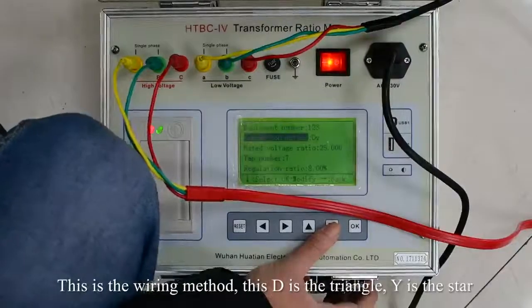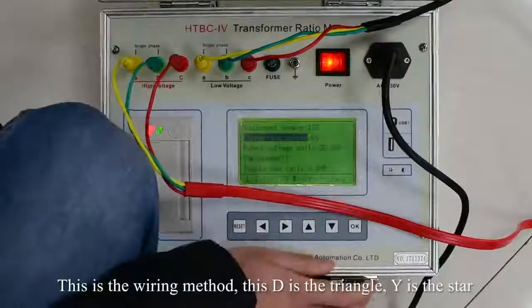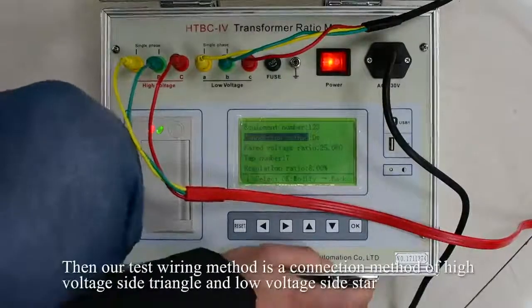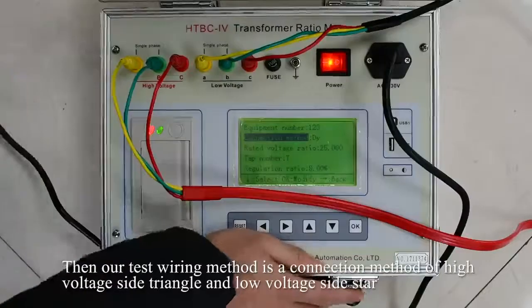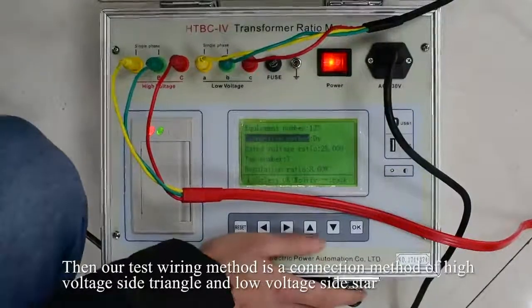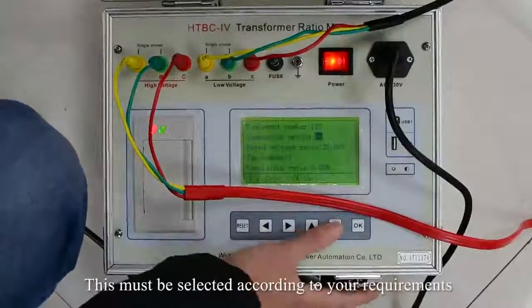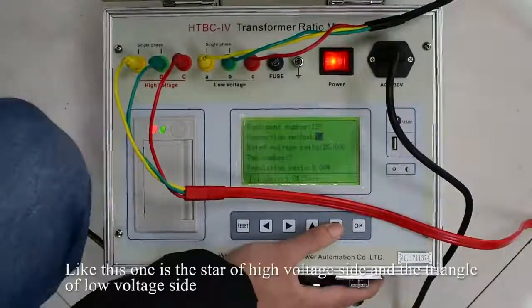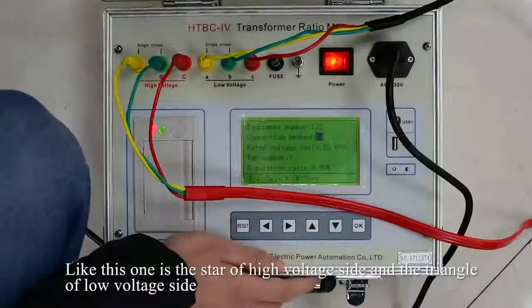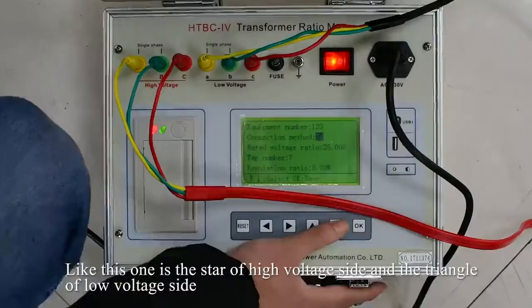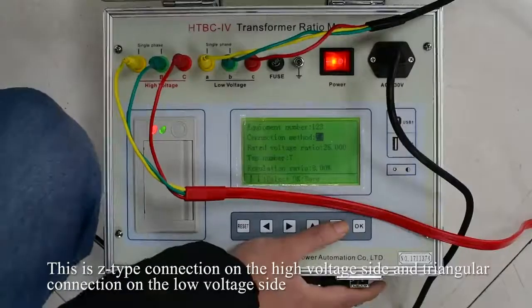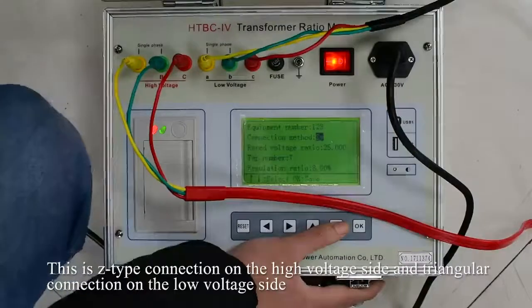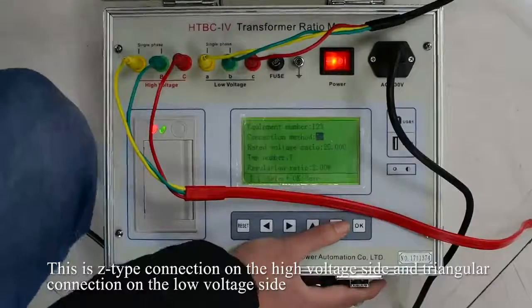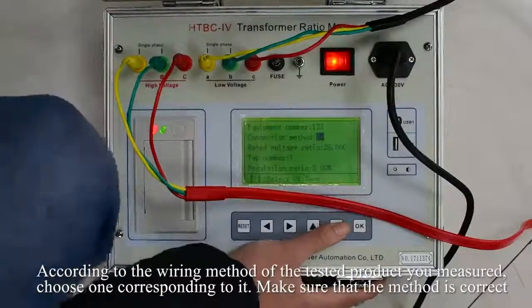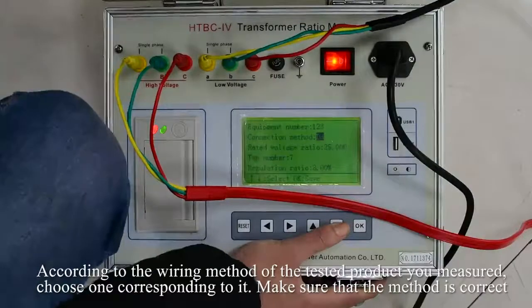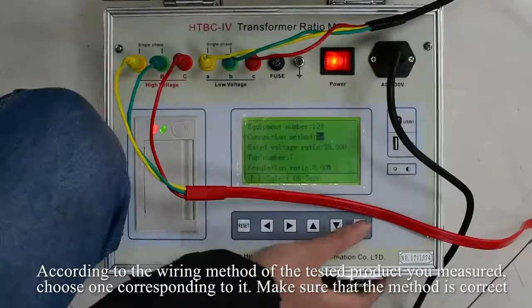This is the wiring method. This D is the triangle. Y is the star. Then our test wiring method is a connection method of high voltage side triangle and low voltage side star. This must be selected according to your requirements. Like this one is the star of high voltage side and the triangle of low voltage side. This is Z-type connection on the high voltage side and triangle connection on the low voltage side. According to the wiring method of the tested product you measured, choose the one corresponding to it. Make sure that the method is correct.